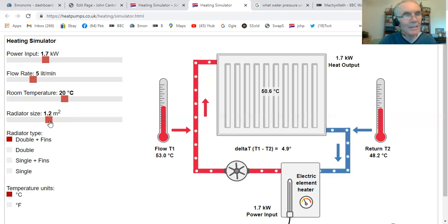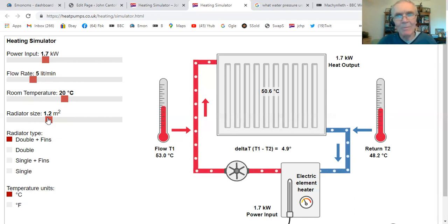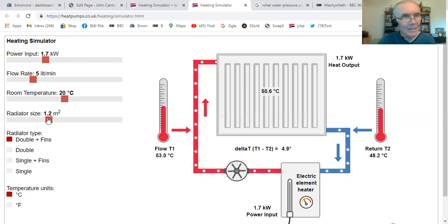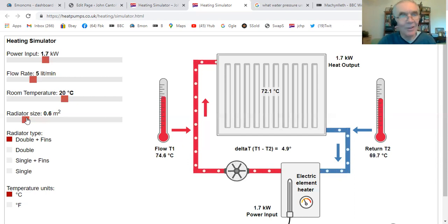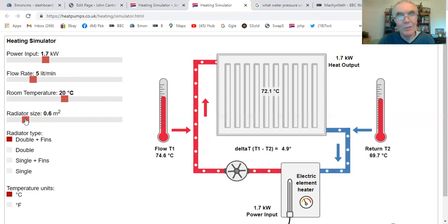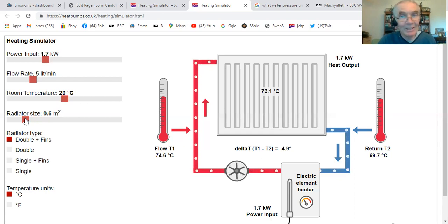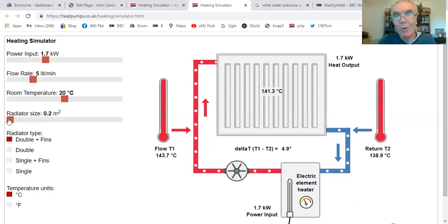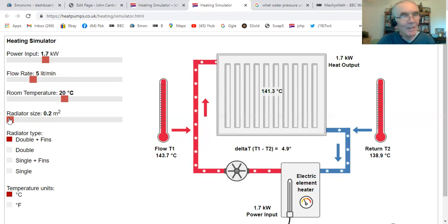Let's look at the radiator size, because we can change the size and type. At the moment it's at 50 degrees — fairly hot. Let's make it smaller. If we make the radiator smaller, it gets hotter, and that's what we'd expect. Less area means it has to get up to a higher temperature to dissipate 1.7 kilowatts. If it's very small, it's got to get up to 143 degrees, which is pretty dangerous — don't try this at home, that would cause pressure in the system.